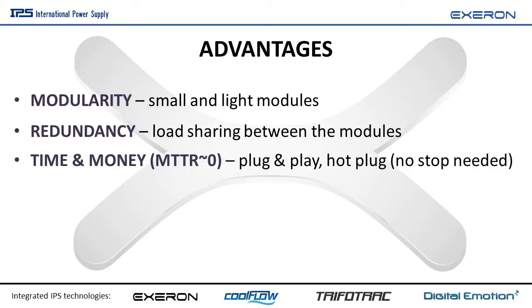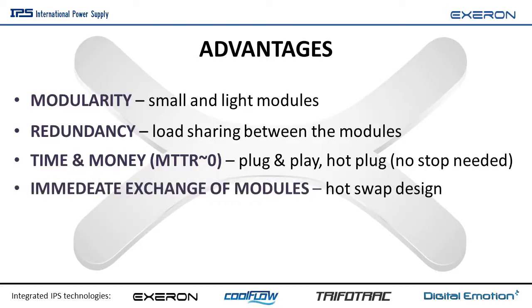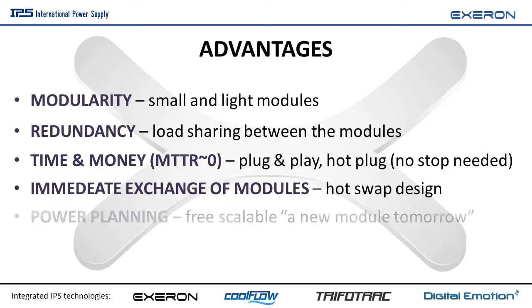EXERON is time and money saving. The MTTR, mean time to repair, is practically zero. This is the time in which a module is not working. All you need to do is exchange the failed module with a new one, just by pulling it out, without any tools, and without even stopping or shutting down the system. The new module is plugged in under voltage, and after that it synchronizes with the other modules and shares the load with them immediately.